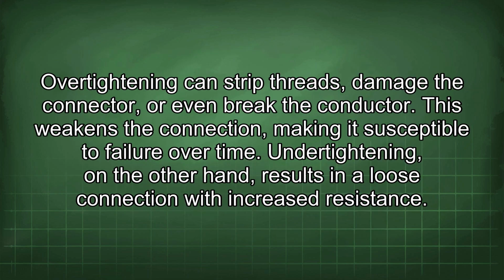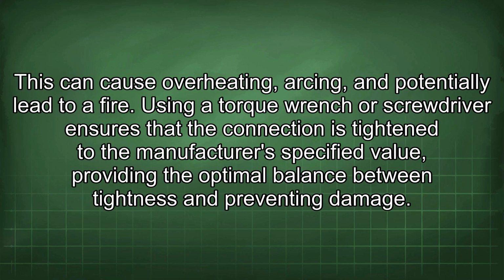Over-tightening can strip threads, damage the connector, or even break the conductor. This weakens the connection, making it susceptible to failure over time. Under-tightening, on the other hand, results in a loose connection with increased resistance. This can cause overheating, arcing, and potentially lead to a fire.